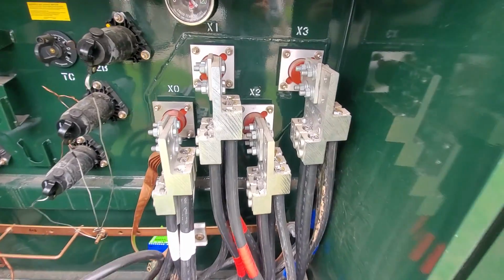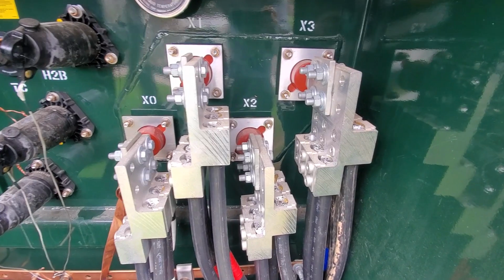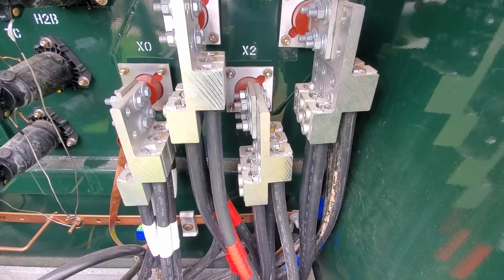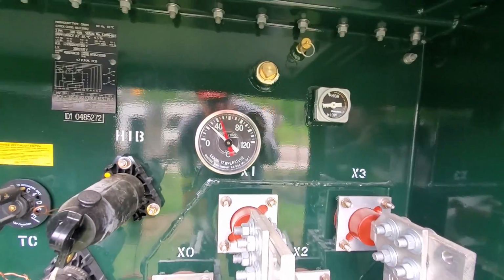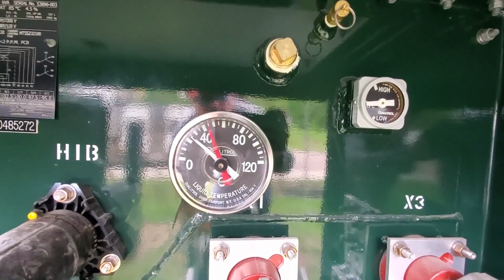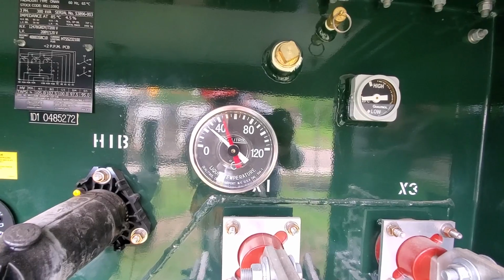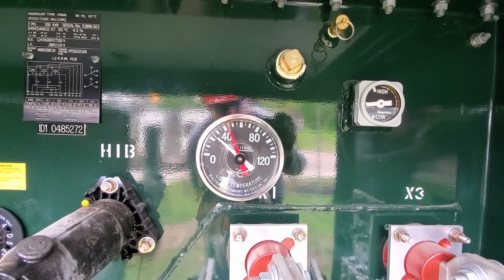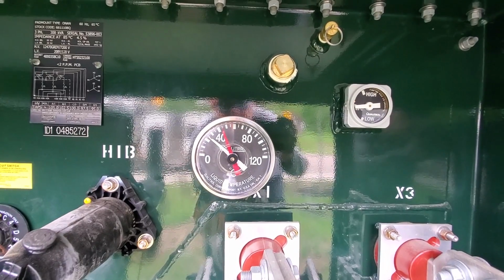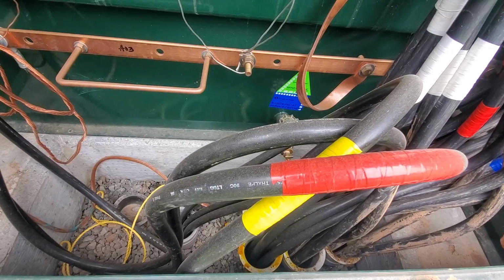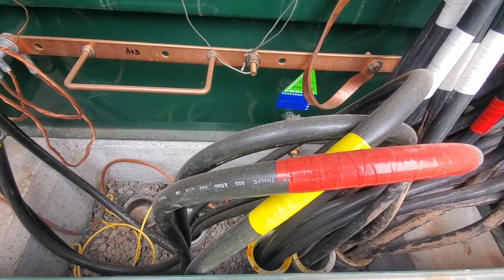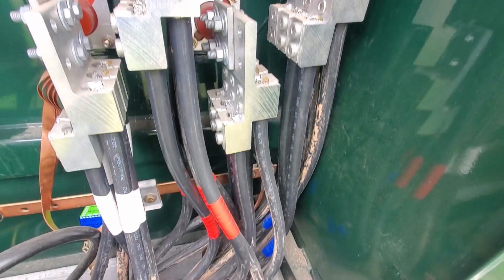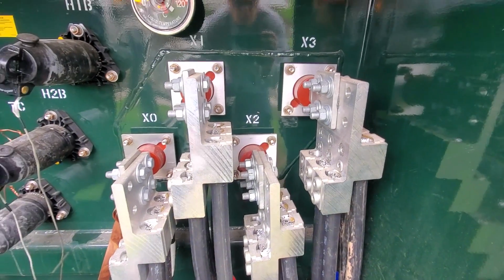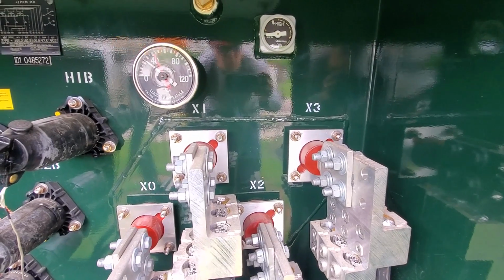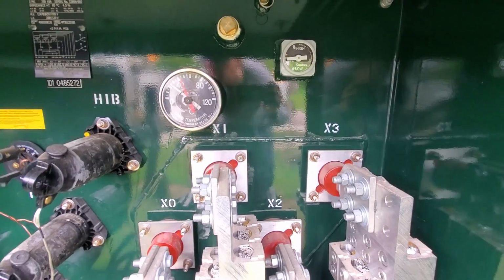You're looking for any connections that show signs of overheating or arcing, both on the primary and secondary. We also have some gauges - want to make sure the transformer didn't get extremely hot at any point. The current temperature is shown by the white arrow, and the red is the max this transformer has ever seen. We do want to make sure all the grounds and bonds are in place. This all would have been done during the initial installation, and there's no reason for any of that to have changed - the only thing that would affect it is vandalism, and it's pretty clear here that hasn't happened.